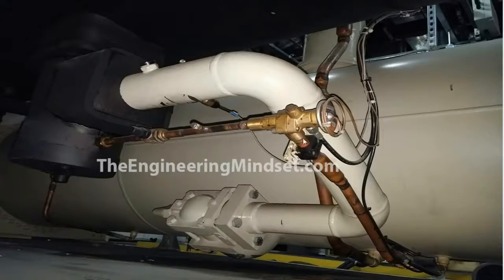To control this flow, we've got the pilot operated thermal expansion valve, and that is also fed refrigerant from the base of the condenser. This flows through this tube here into the valve. The valve decides if it can flow in or not. That flows through into the base of this, the main expansion valve, and this flow is what controls the main valve.